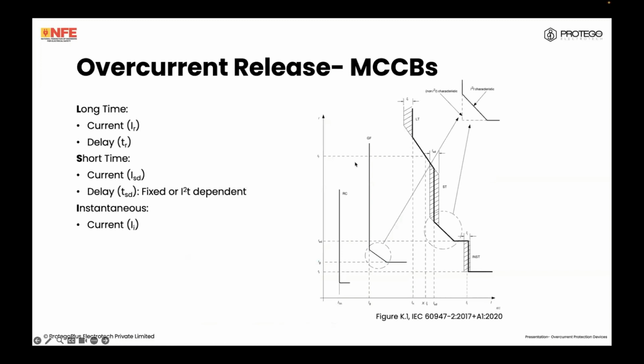When it comes to the MCCB, let's focus on this curve here. There is the L, S, and I. The long time current is given as a percentage of the nominal current. So if you have a 100 ampere MCCB, I may choose to have it act as a 40 ampere MCCB. So I will say 0.4 times IN, that is my long time current. And then I can have a long time delay, which is if I have a high starting current in that circuit as an inrush current, it will delay the trip of the long time current for a certain amount of time to let that inrush current pass. If not, then it will trip after that time, because you do not want these to trip prematurely under fault-free conditions.